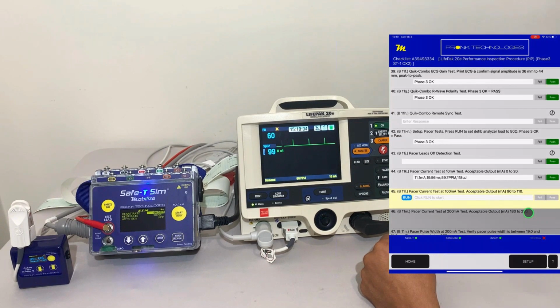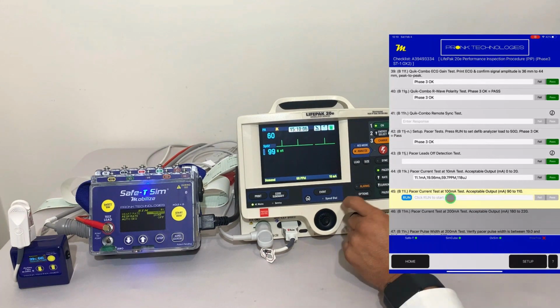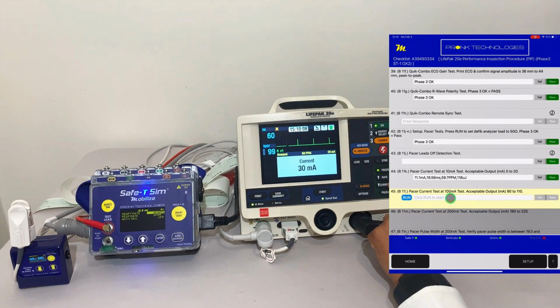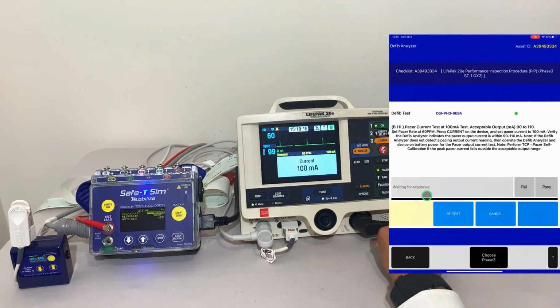The next measurement wants us to set it to 100 milliamps. Go ahead and do that here on the device. We've set that, let's run that test. The analyzer's going to sample it for a certain period of time, collect a stable sample, and then report back the results. Again, we have a result here of 101.2 milliamps, and that's within the target of 90 to 110. We've passed this test. On to the next one.